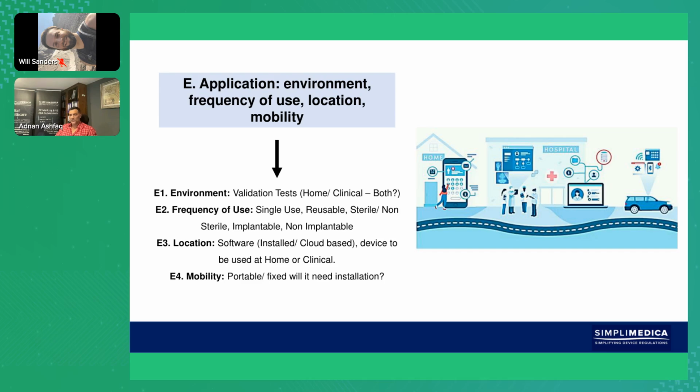For the frequency of use, if it's single use, is it disposable? How do we dispose of it? Is that environmentally friendly? And remember, risk management is not just about harm to people, it's also harm to the environment. So we have to make sure that we have all those risks identified and then use the correct language in the instructions for use that tells us the correct disposal of the device.